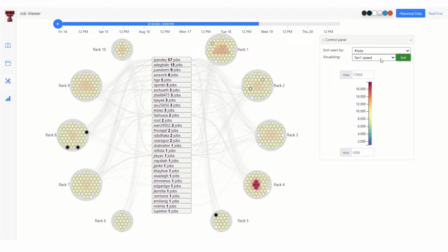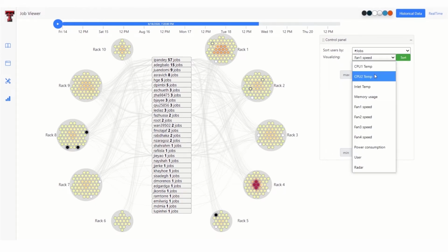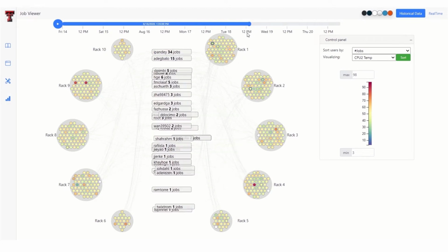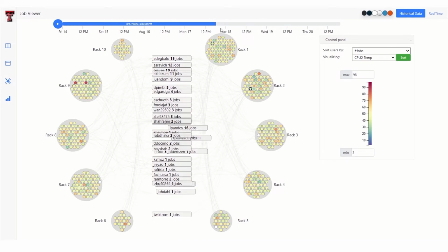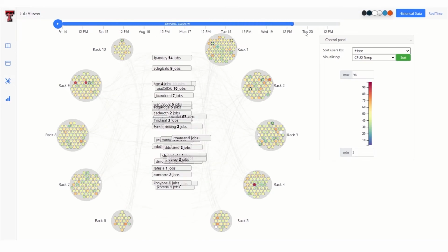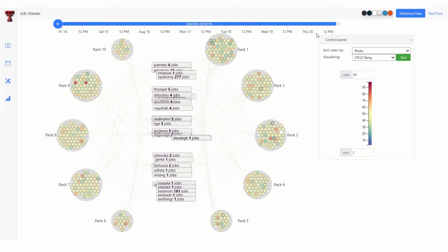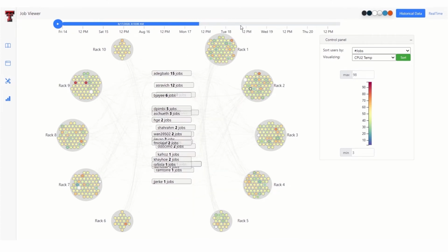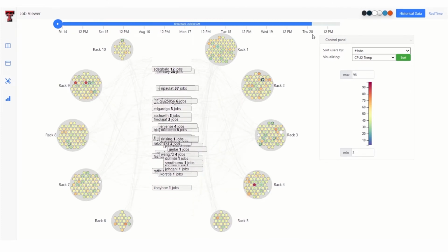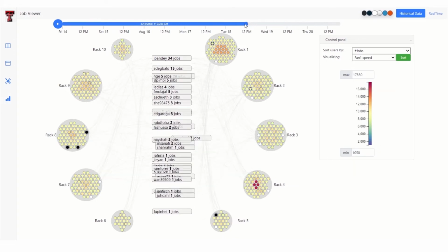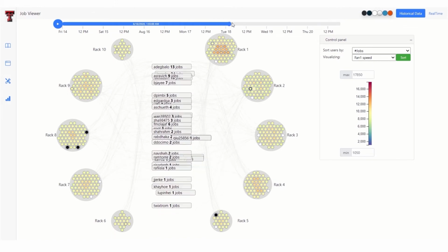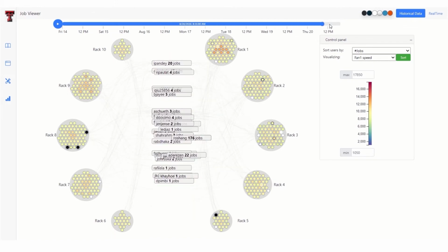CPU2 temperature of node 10.101.4.33 started increasing to reach its peak at 11:35. At 11:35, we can see that the 4 fan speeds of the 4 nodes also grow, before reaching the peak at 11:40. Usually, the CPU2 temperature will be lower than the CPU1 temperature due to the cooling arrangement of a node. However, node 10.101.4.33 has a high CPU2 temperature. When CPU2 temperature drops at 11:45, the 4 fan speeds of the 4 nodes also reduce.